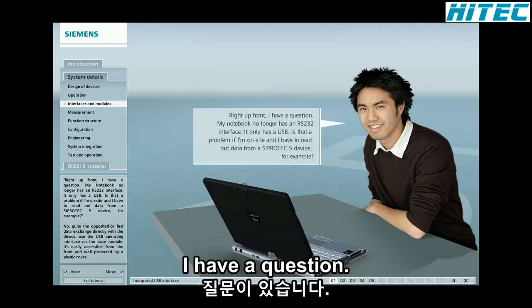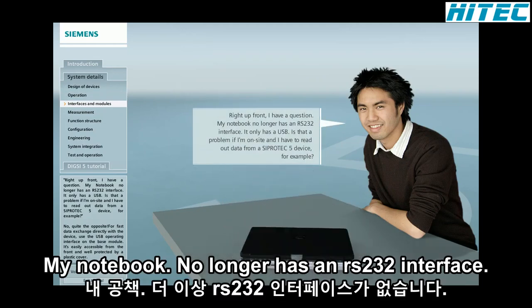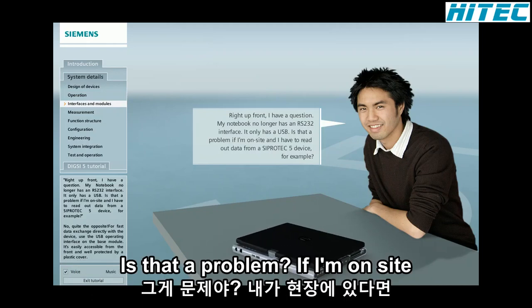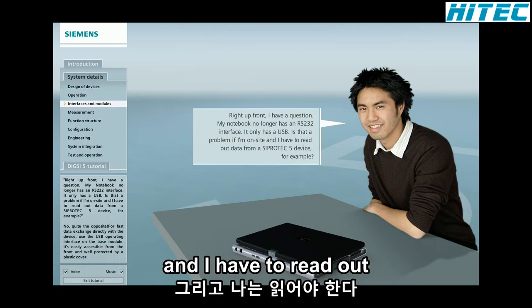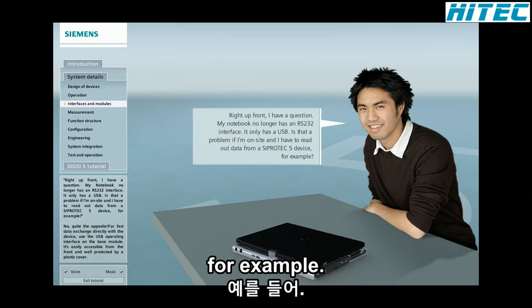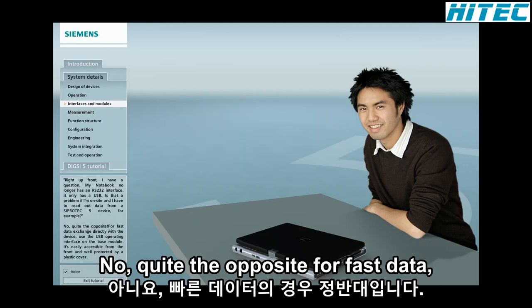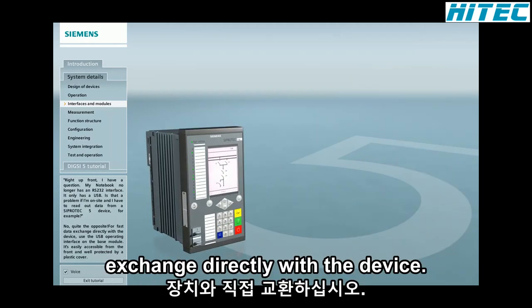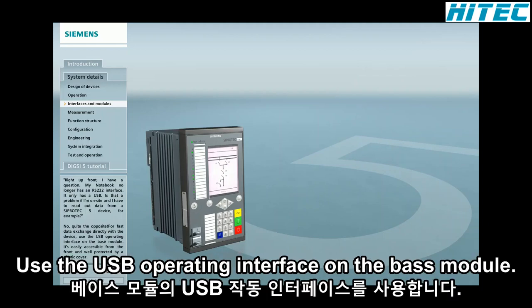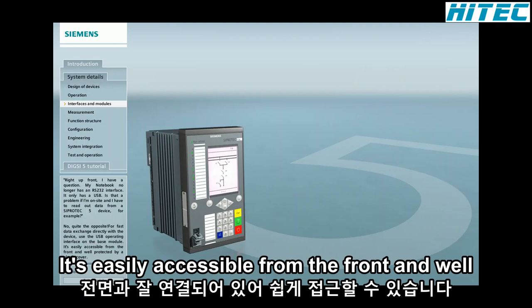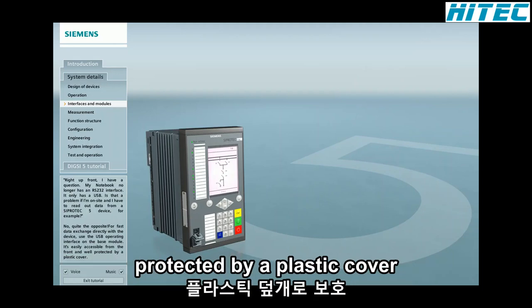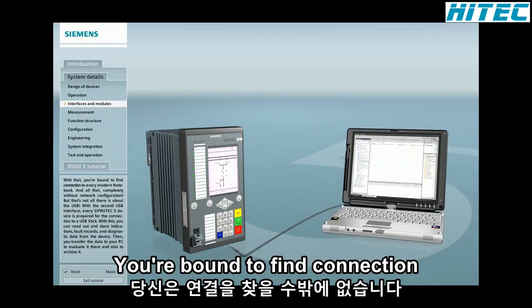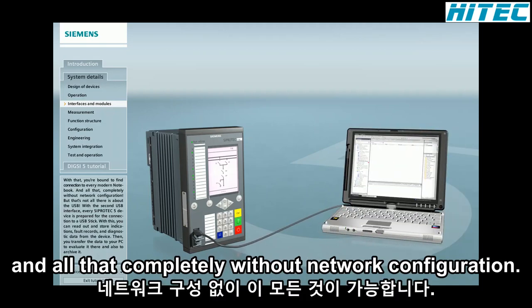Right up front, I have a question. My notebook no longer has an RS-232 interface. It only has a USB. Is that a problem if I'm on site and I have to read out data from a SIPROTEC 5 device, for example? No, quite the opposite. For fast data exchange directly with the device, use the USB operating interface on the base module. It's easily accessible from the front and well protected by a plastic cover. With that, you're bound to find connection to every modern notebook, and all that completely without network configuration.